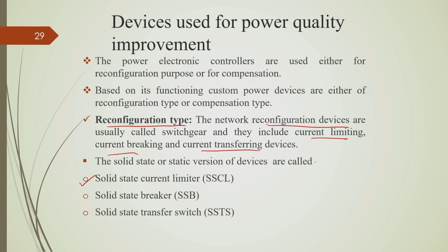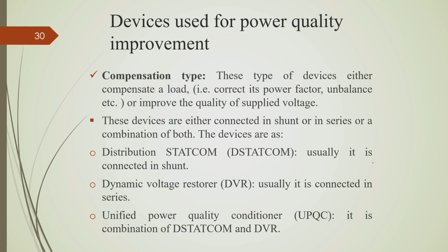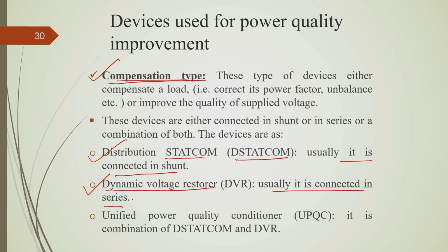So, these are some reconfiguration type custom power devices, which are called the solid state current limiter, solid state circuit breaker, and solid state transfer switches. And we have some power electronics based compensation devices specifically constructed to mitigate these power quality problems. They are named distribution STATCOM or D-STATCOM. This is usually a shunt connected device used for mitigation of harmonics and to provide reactive power compensation, and it has multiple functionalities. Similarly, there is a custom power device called the dynamic voltage restorer. It is usually a series connected power electronic device, which is used to mitigate voltage sag, voltage swell and many other power quality problems. And the unified power quality conditioner, also called UPQC, is a combination of D-STATCOM and DVR. So, they have dual functionalities.